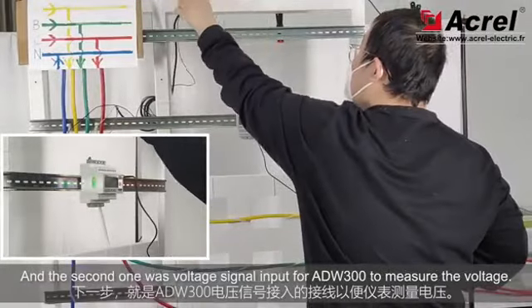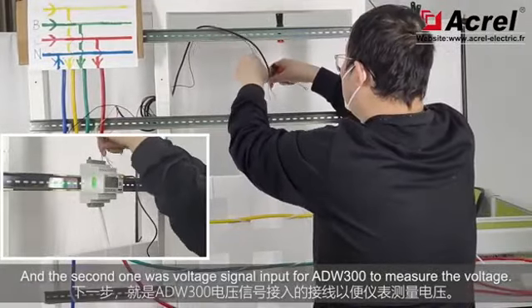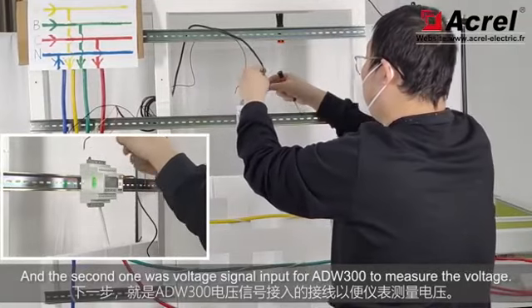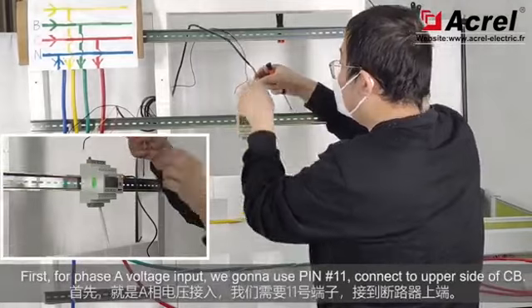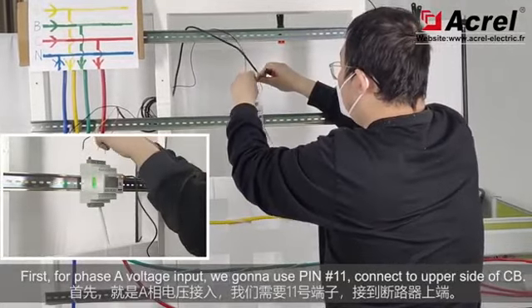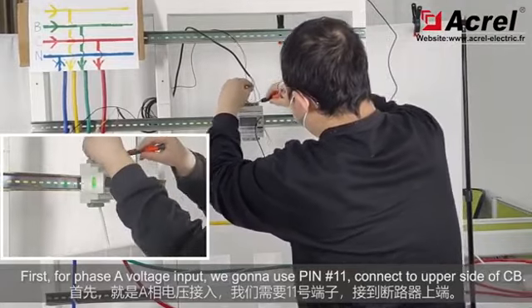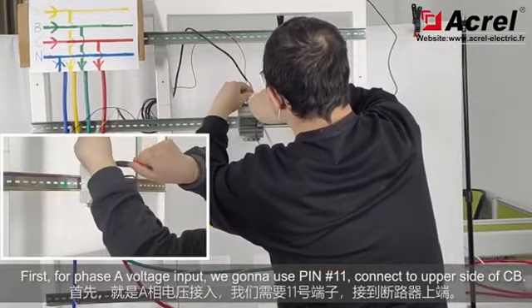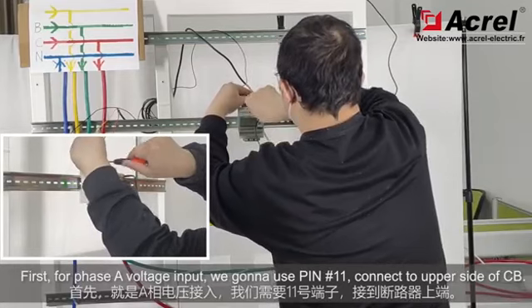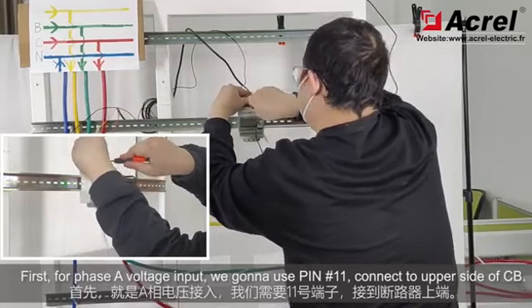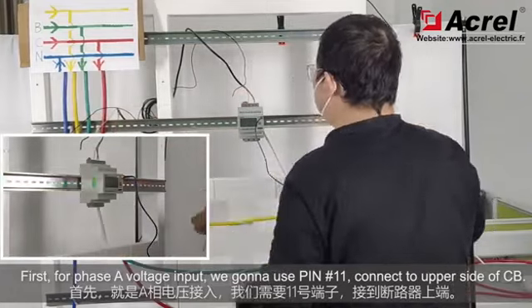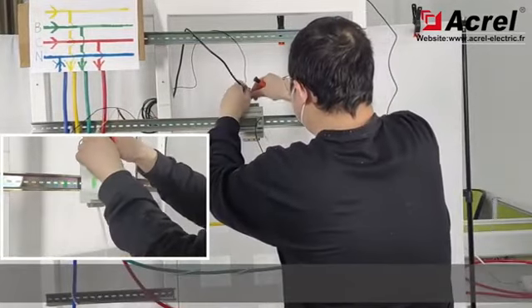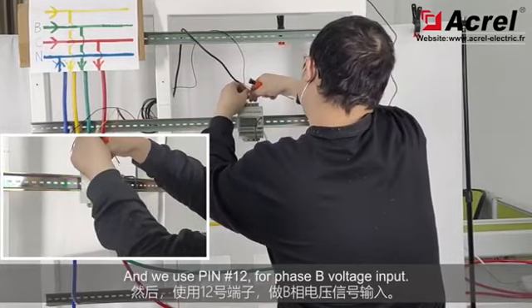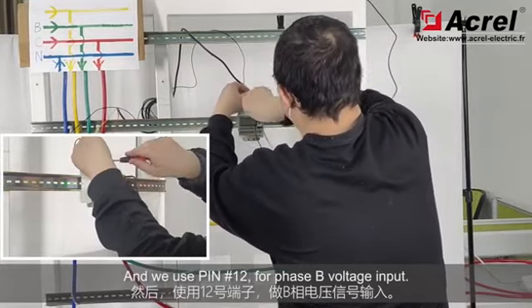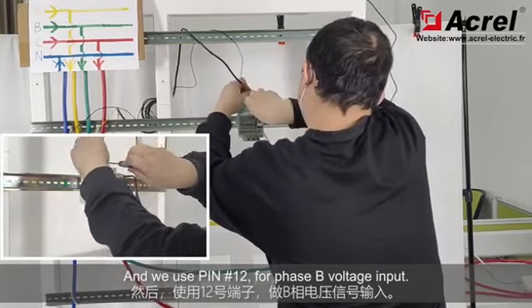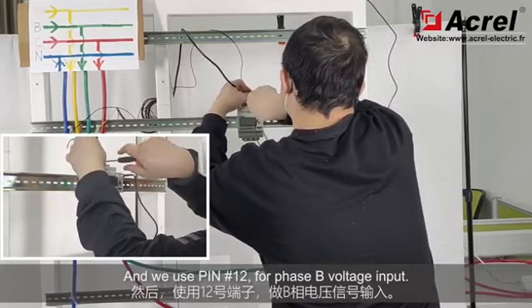The second one is for voltage signal input, for the ADW300 to measure voltage. First, for phase A power voltage input, we use pin 11, connecting it to the upper side of the CB. And we use pin 12 for voltage phase B input.